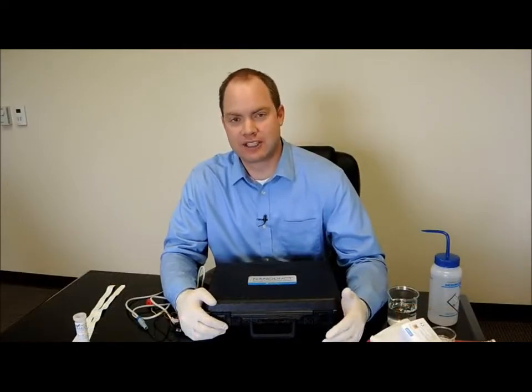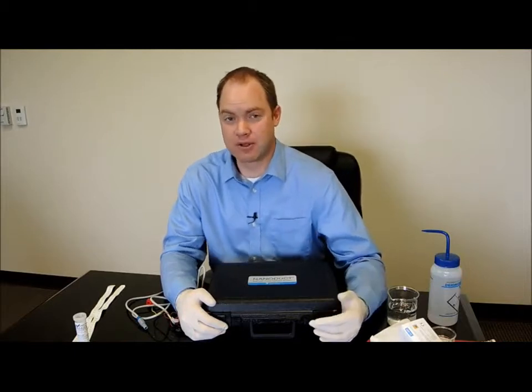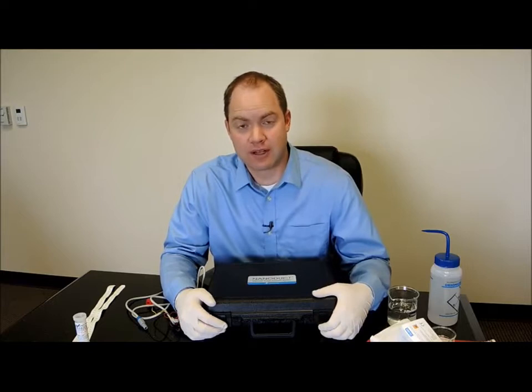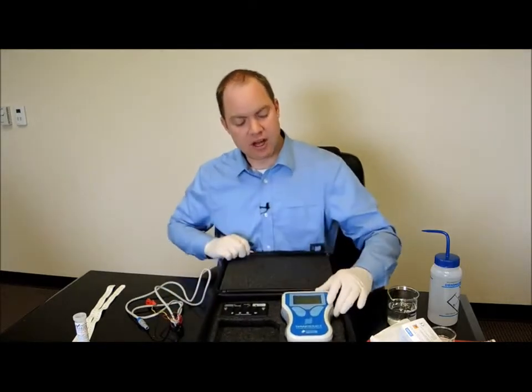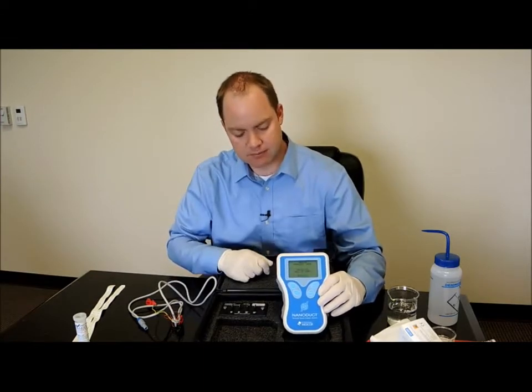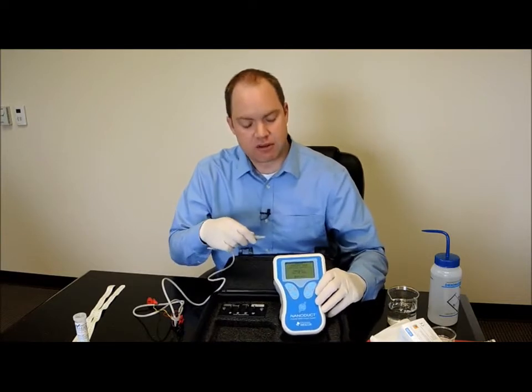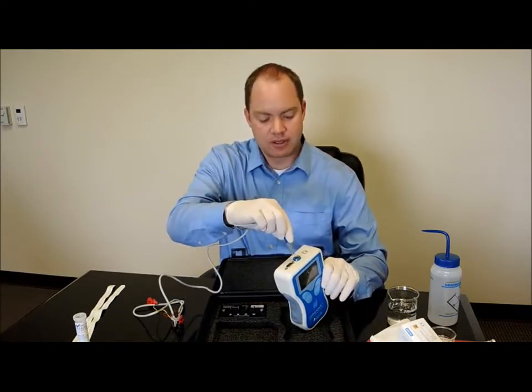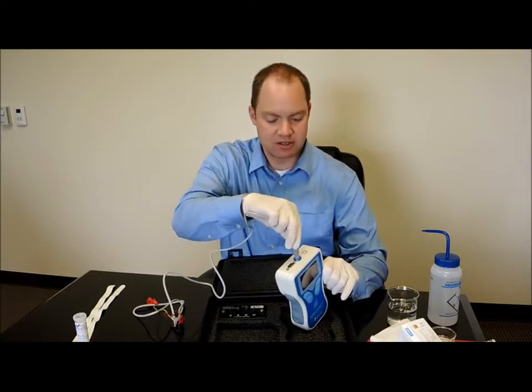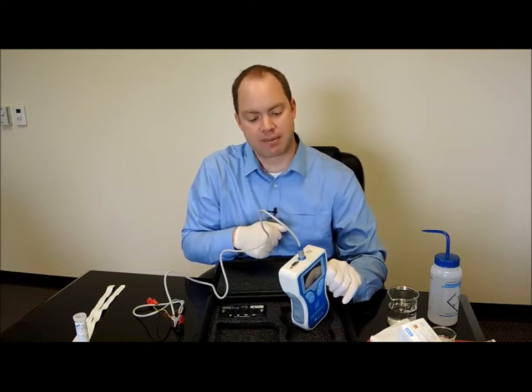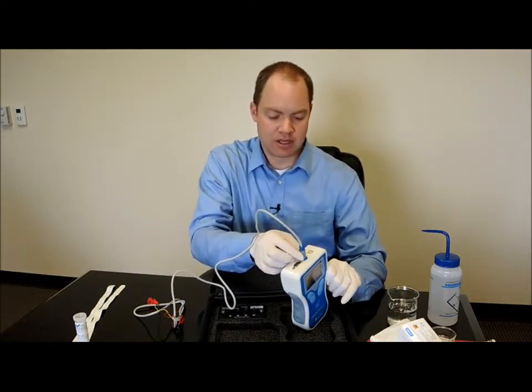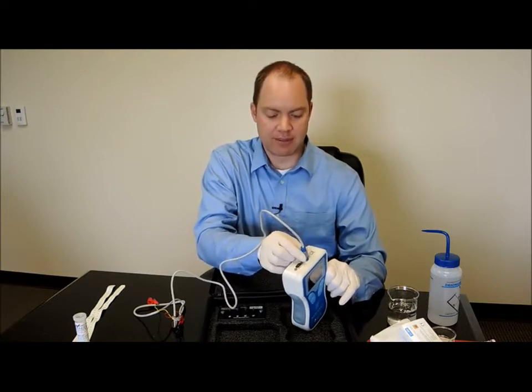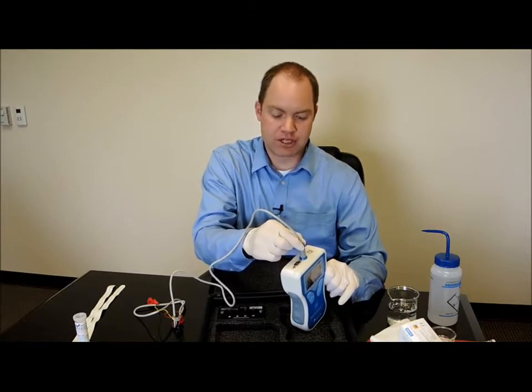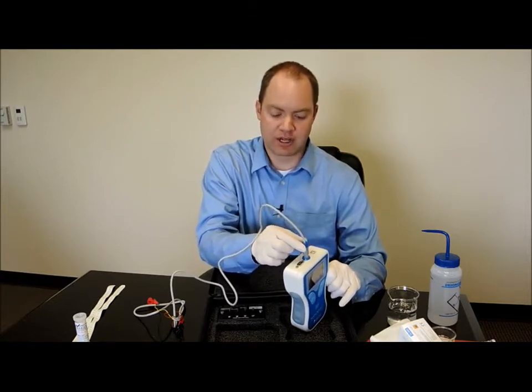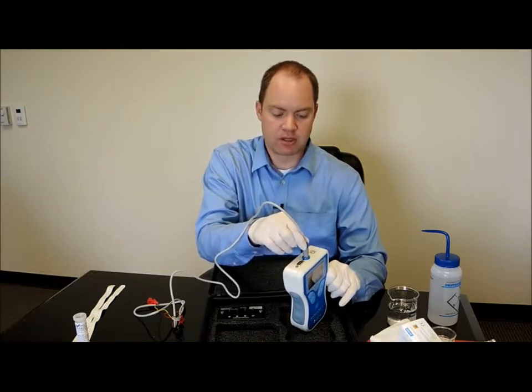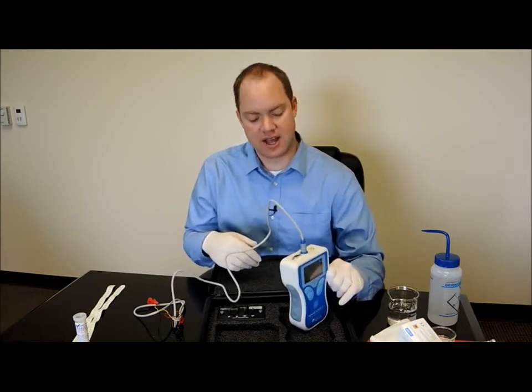Now that I've described to you all the accessories and supplies that you'll need with the Nanoduct, I'll show you the proper use of the Nanoduct. And the first thing you do is you calibrate the Nanoduct. So you turn on the Nanoduct by pressing the on button, and it does a software boot up. You connect the cable to the top of the Nanoduct, and the cable is keyed, and so it can only fit one way, and it connects with a nice snap like you heard. To release the cable, you pull up on the gray portion of the cable like so. If you pull up on the blue portion, it won't release. So you pull up slightly on the gray portion and it will release, and that's how you release the cable. To attach it again, you just press straight down and you hear a nice snap.